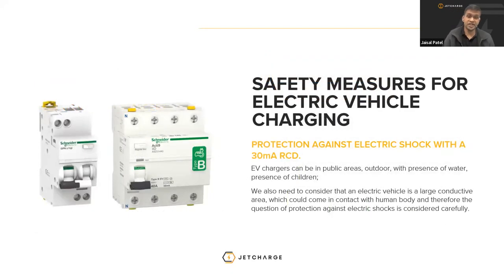So now we go on to the safety measures that we spoke about earlier, protection against electric shock. Typically an EV charger is located in very public areas, outdoors in the presence of water, children, where the possibility of electric shock can be quite high. So we need to consider that when we design our protection against electric shock. We typically use what's called a 30 milliamp RCD.